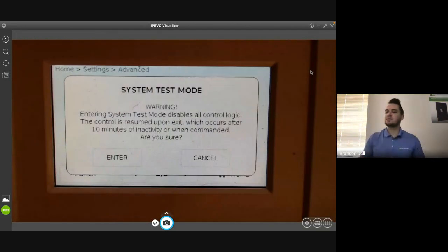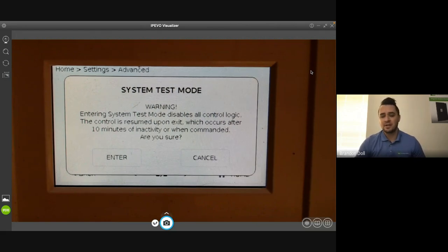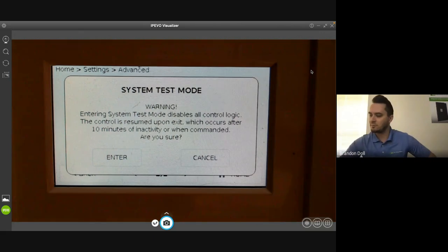And then the system test mode. This is a really cool feature for commissioning purposes. What it does is it takes all control logic out of the thermostat and puts it into your hands. So it's kind of giving you a warning here saying, hey, you better know what you're doing, because you're going to be able to open and close, send milliamperage signals out. So you better know what you're doing.